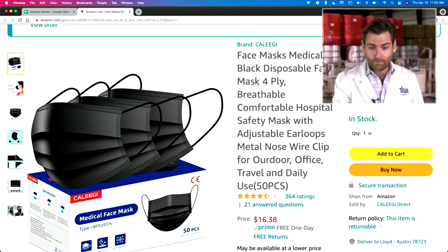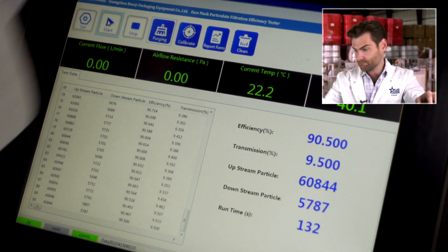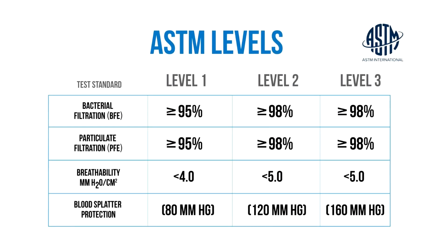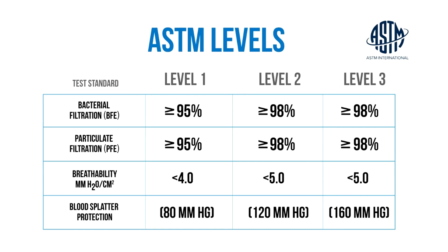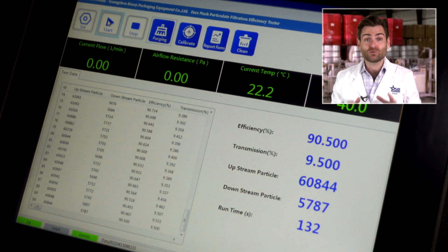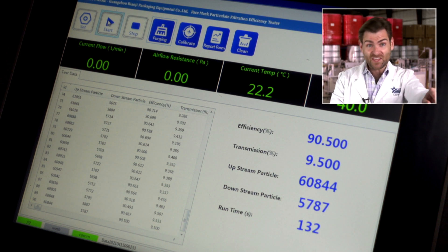This one is the brand Caleegi — same as on the box and on screen. They made the claim it's a Type 1 mask, but does it hold up? 90.5 percent. That is not 95 — 90.5. A Type 1 mask under the EU standard requires 95 percent, very similar to ASTM Level 1, Level 2, or Level 3 — all at 95 percent bacterial and particulate filtration. This entire lab is designed to test to that standard, and they have failed that standard. So I've got to call them out — that's some BS. They are straight-up lying to you. These mouth covers are not Type 1 mouth covers.